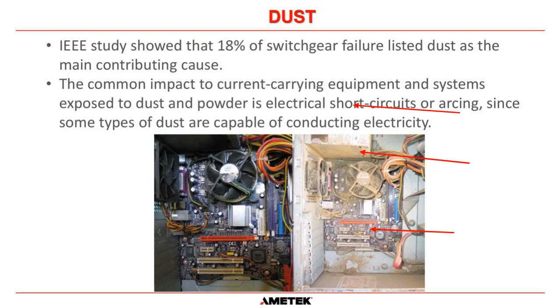An example of that, I don't have any pictures of it. I remember a UPS that was on a platform in the North Sea, and it was more a commercial type UPS. It was probably not where it should have been installed. And that UPS basically had a fan on the front of it that pulled in air directly across the main circuit board and the heat sinks for the power transistors, and then out the back of the UPS. And there wasn't any filtering on that UPS whatsoever. And it just so happened there was an air intake very, very close to where that UPS was.